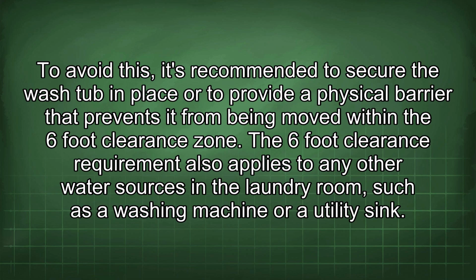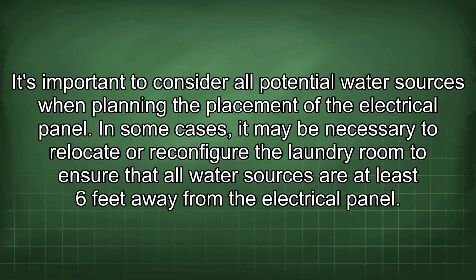The 6-foot clearance requirement also applies to any other water sources in a laundry room, such as a washing machine or a utility sink. It's important to consider all potential water sources when planning the placement of the electrical panel. In some cases, it may be necessary to relocate or reconfigure the laundry room to ensure that all water sources are at least 6 feet away from the electrical panel.